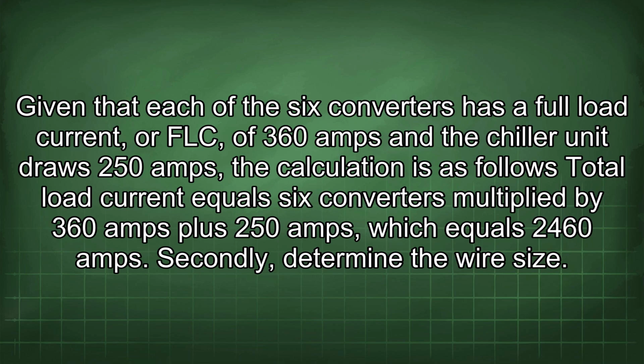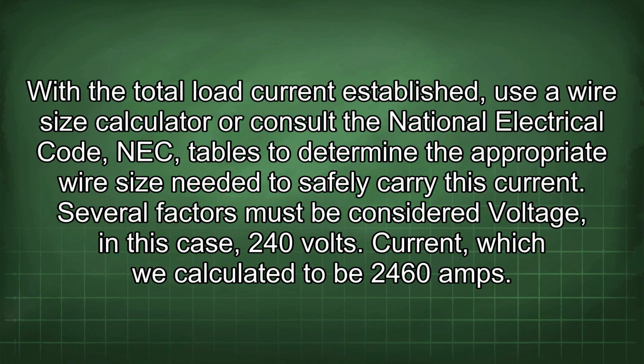Secondly, determine the wire size. With the total load current established, use a wire size calculator or consult the National Electrical Code (NEC) tables to determine the appropriate wire size needed to safely carry this current. Several factors must be considered. Voltage, in this case 240 volts.